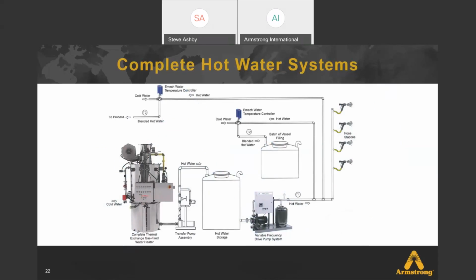So the heater itself, the bottom can area where you see the small transfer pump coupled, that is not a storage tank, that is a collection basin. As the water drops to the bottom, at your set temperature, you have to move that to an atmospheric storage tank. The storage tank is what starts and stops the heater.